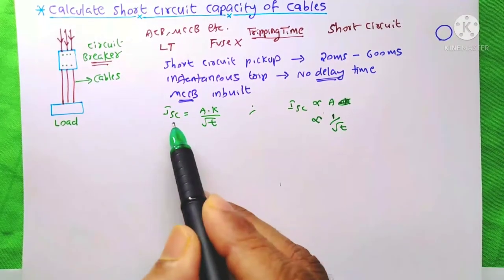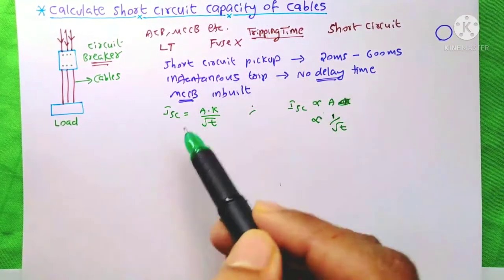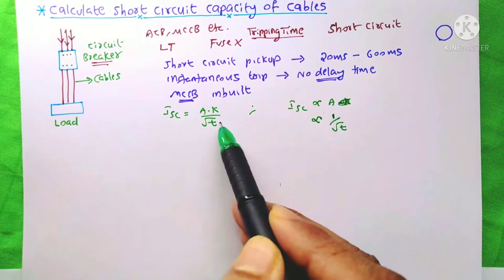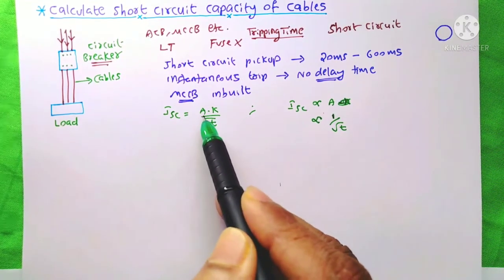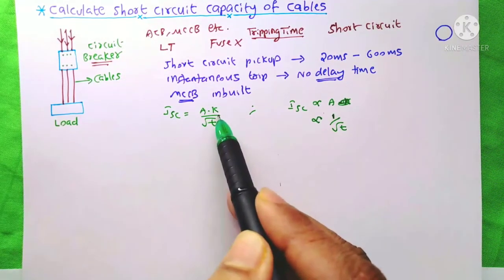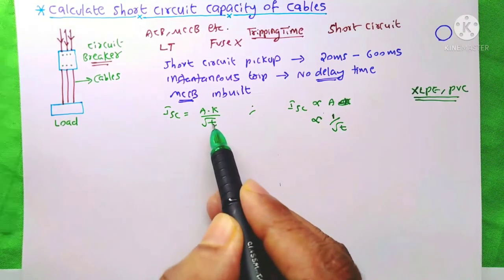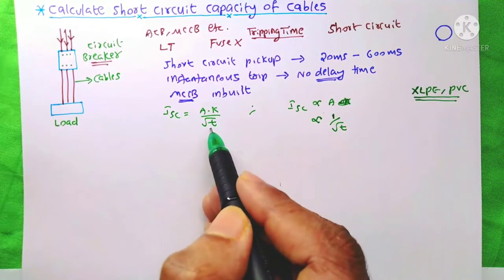The equation for the short circuit current for cables is A×K/√T. A means area of the cable, K is a constant, and T is the tripping time of the circuit breaker during the short circuit.